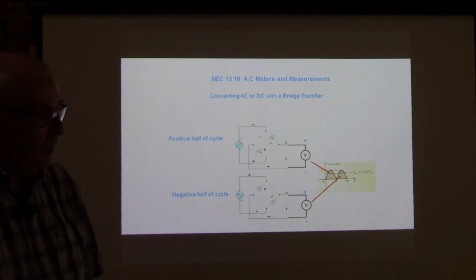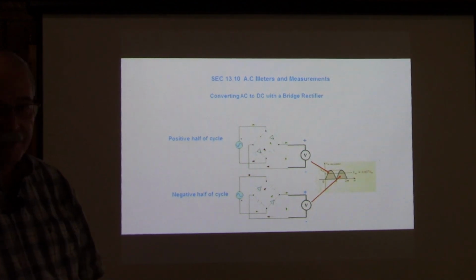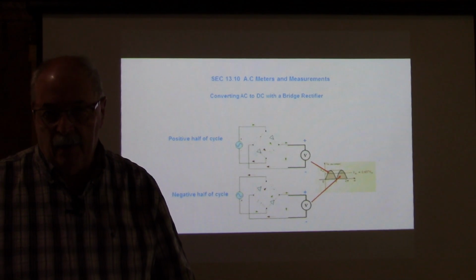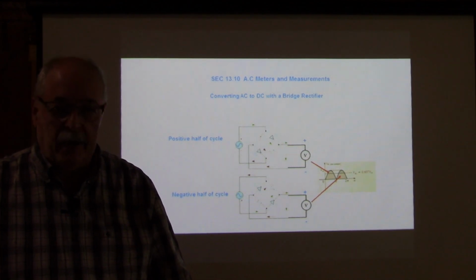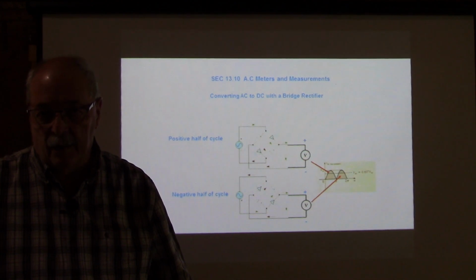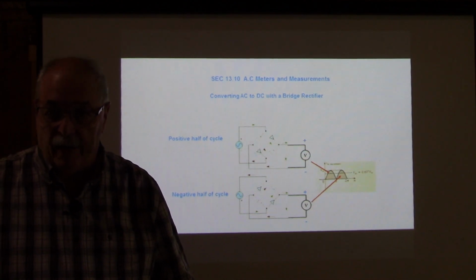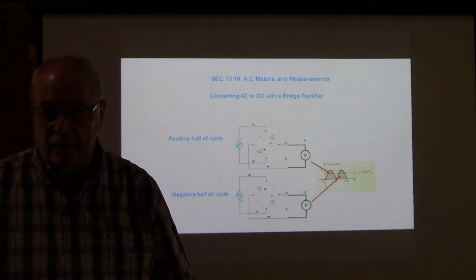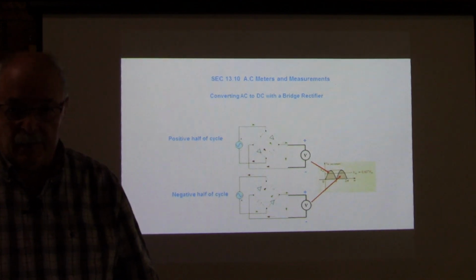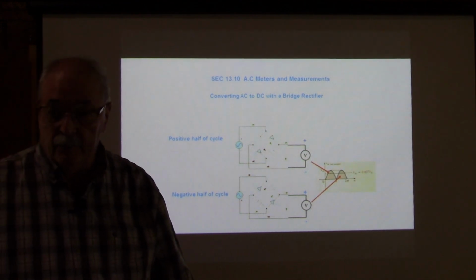So, an interesting example: we have ventilators made in Germany. The translation in the manual was a little messed up. It said that one of the things we were talking about was check valves, and we knew there was no water or pneumatics involved in this, so we realized that they had never converted the check valve to rectifier or to diode.